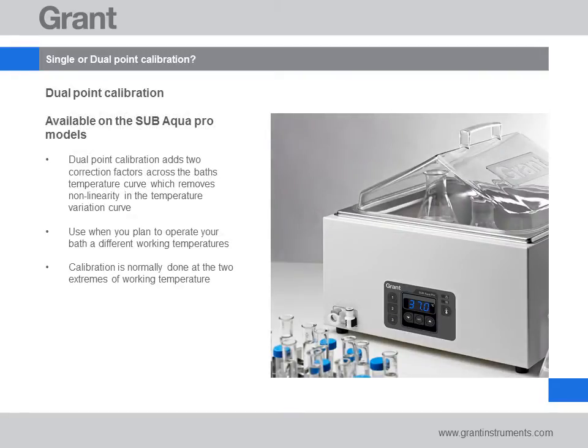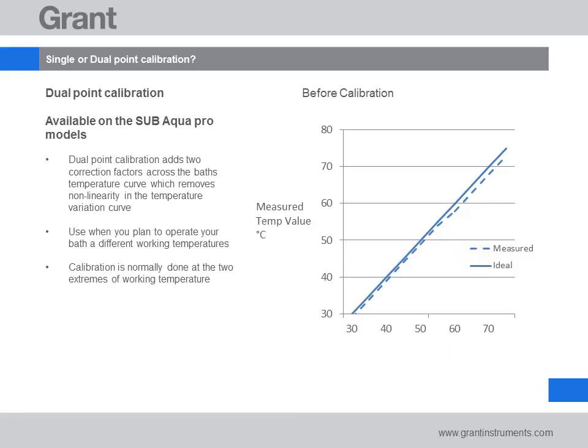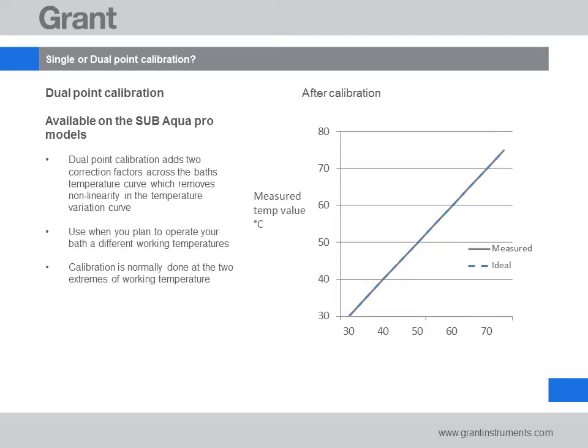Dual point calibration is available on all Sub Aqua Pro models. This allows 2 correction factors to be applied across the bath temperature curve. This is useful when you're routinely using your bath over a range of different temperatures. We'd recommend that you choose 2 extremes of working temperature to make this as effective as possible.